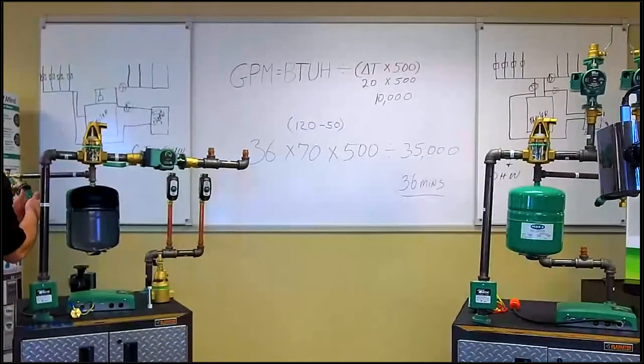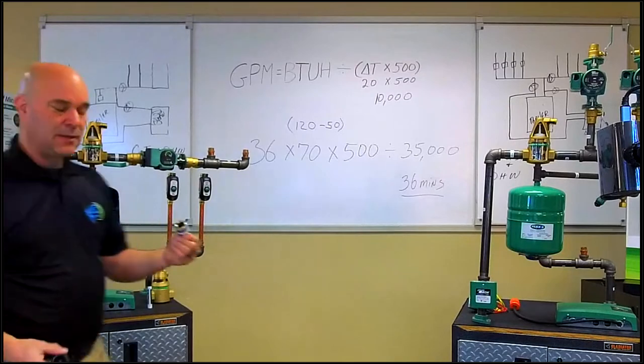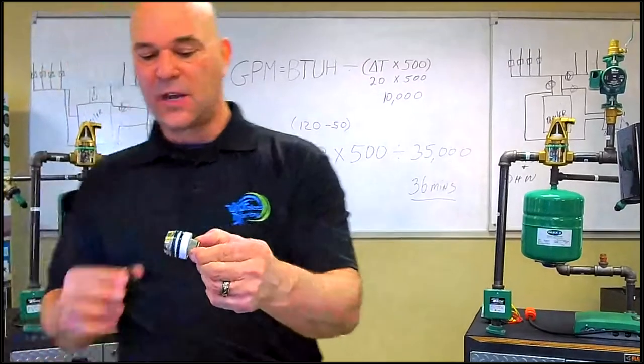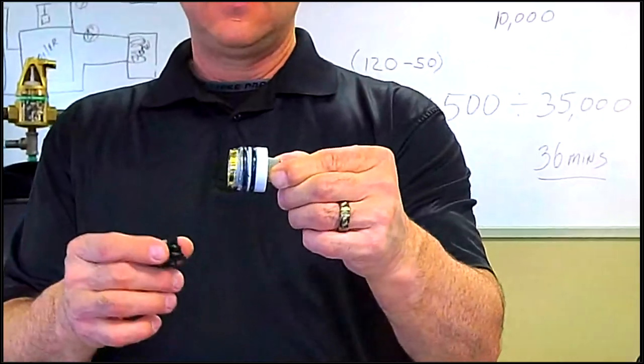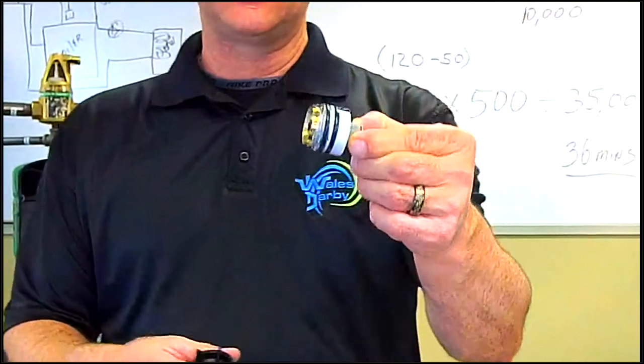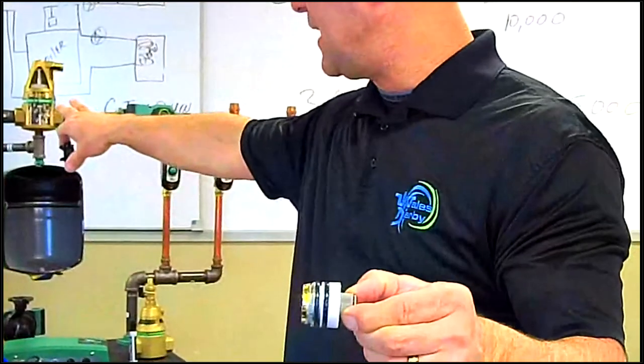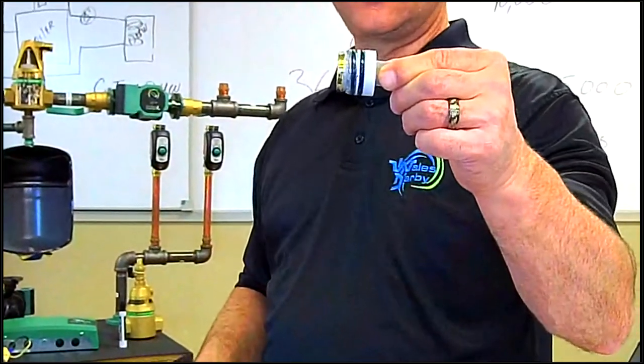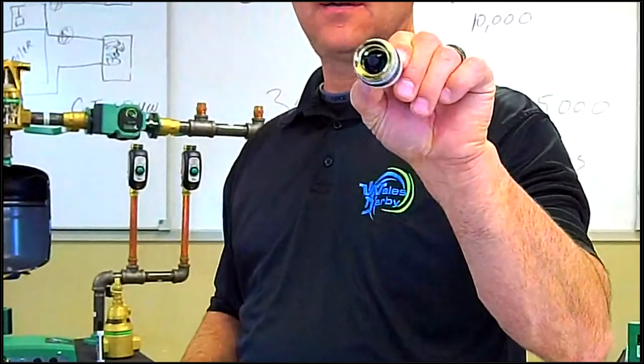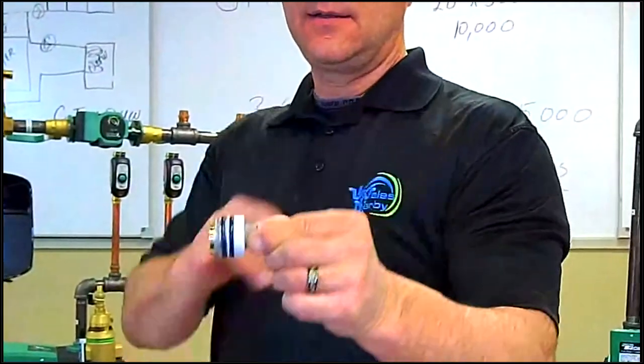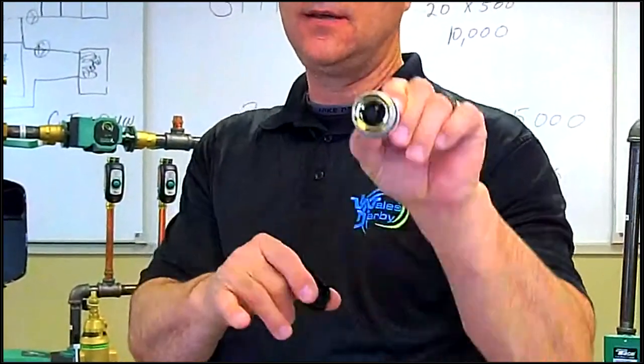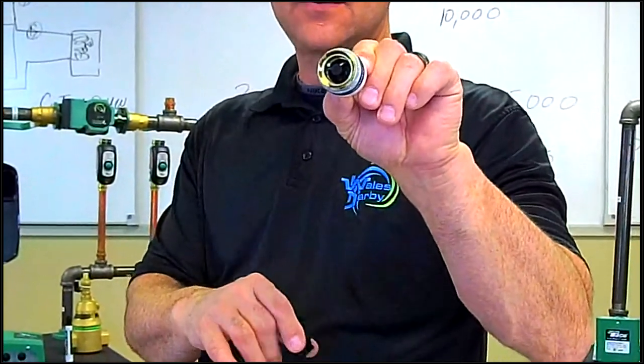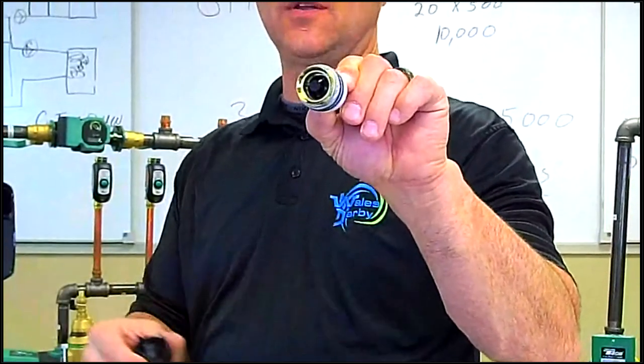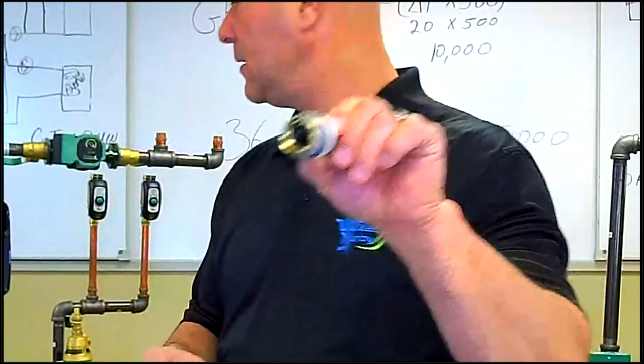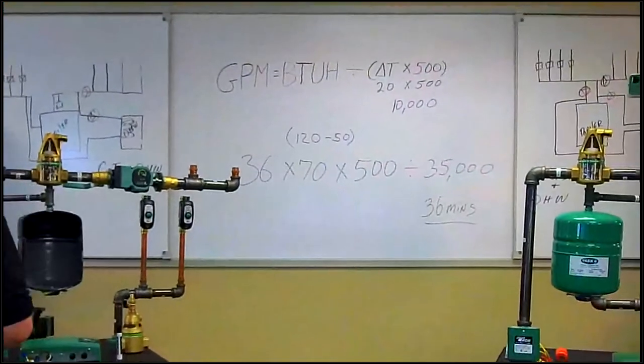And it just goes right back in with a rubber O-ring on it. And then on the other side is the check valve backflow preventer. Again, this is replaceable. So the body will stay on the job and I can replace either the backflow preventer or the feed valve side. This has an O-ring, a screen, and a check valve internally. So if you shut the feed off, it's not going to drain the boiler system like a typical backflow. All right, so it'll keep the pressure on the system.